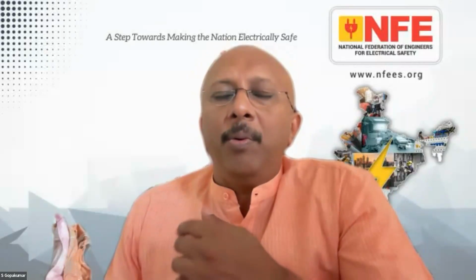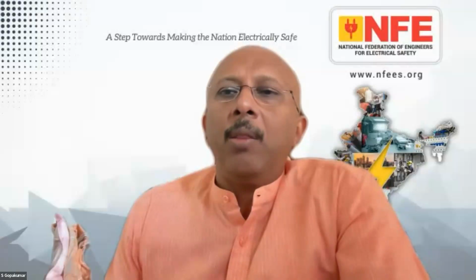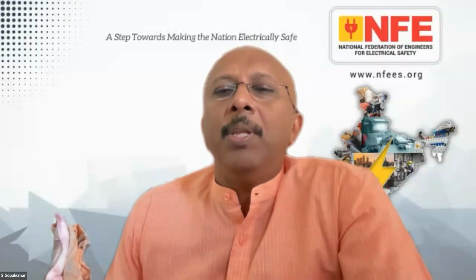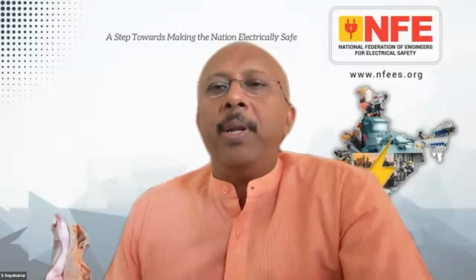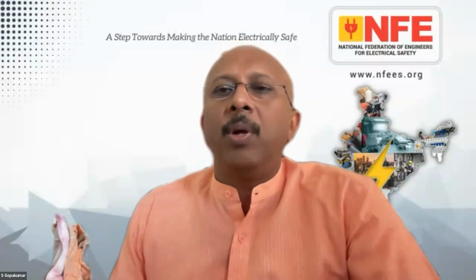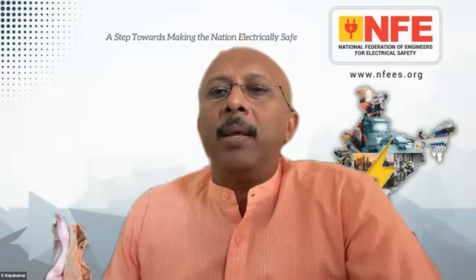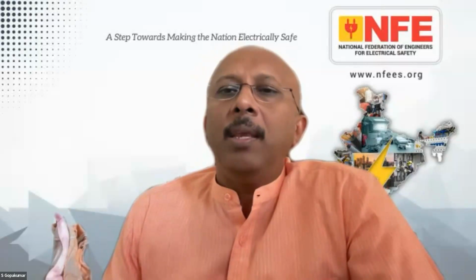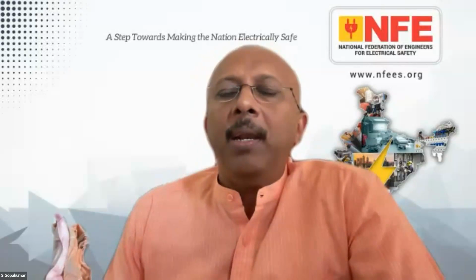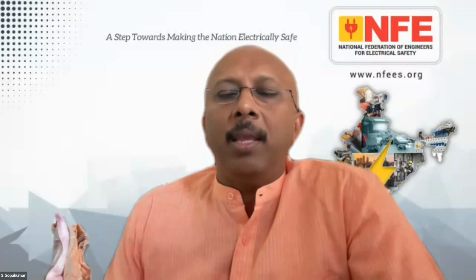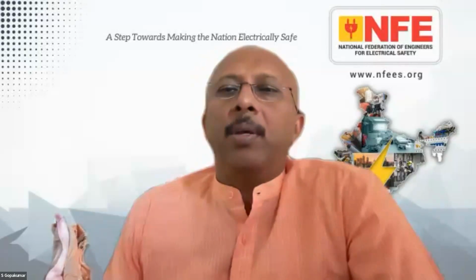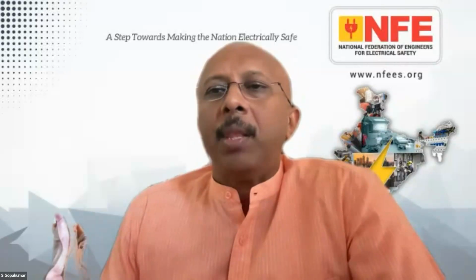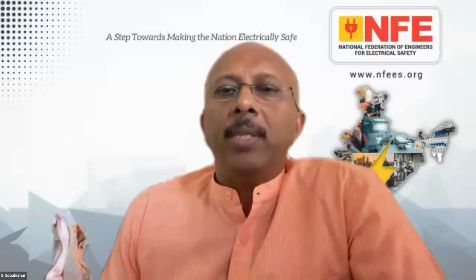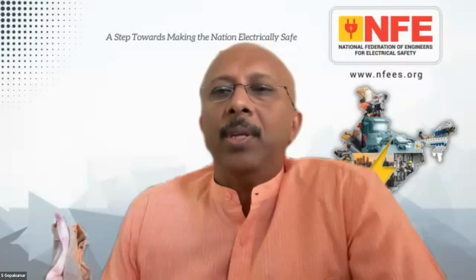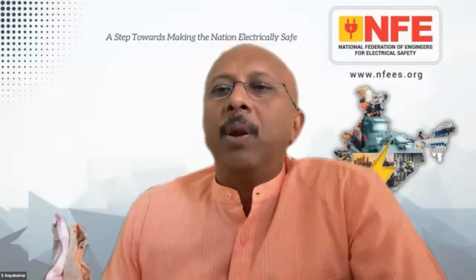So 20 volt drop is too high a voltage drop. Now a low voltage between neutral and earth also means the voltage drop is quite less. That means you have a very low impedance network. You have a strong network. So there are different ways of interpreting it. But nowhere is it written that the neutral to earth voltage shall be maintained to X value. Even if it is 30 volt, your system will work. Your equipment are supposed to work. But 30 volt means your network is having high impedance, voltage drop is too much. So MCBs and protective devices will not work. That is how we should take it up further.